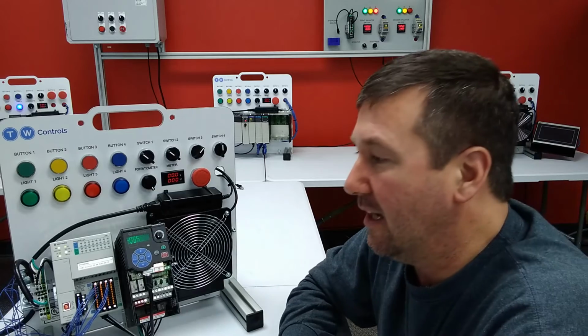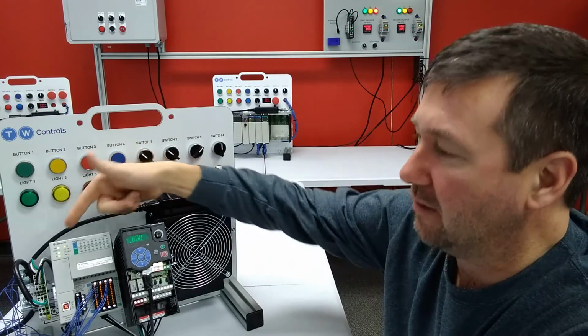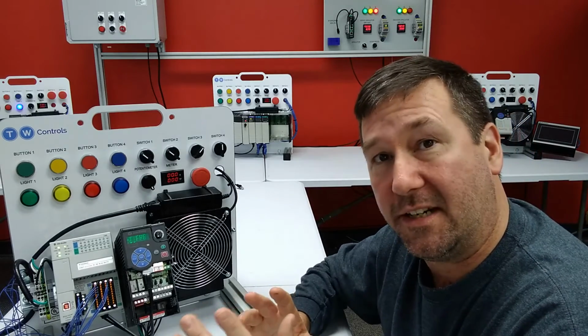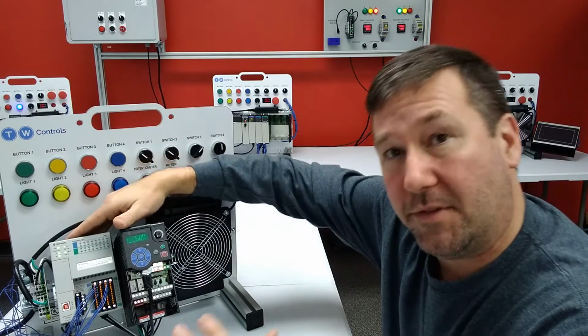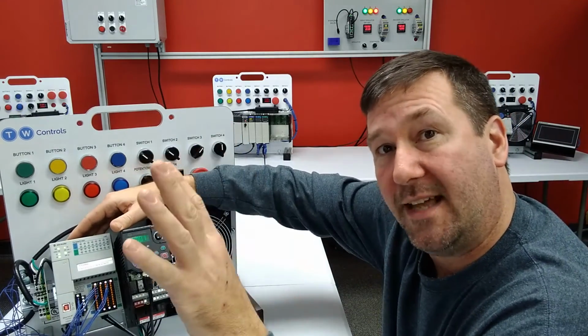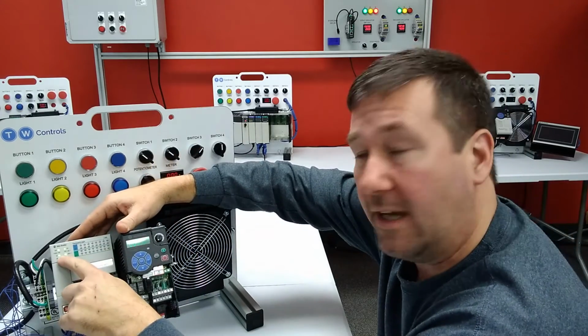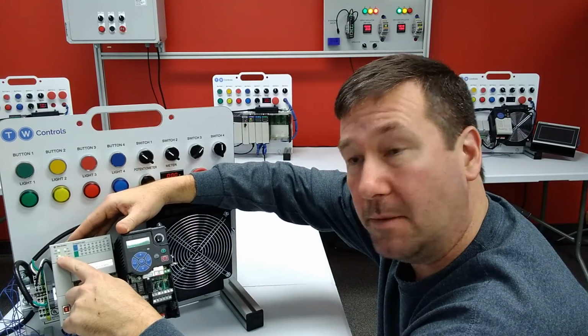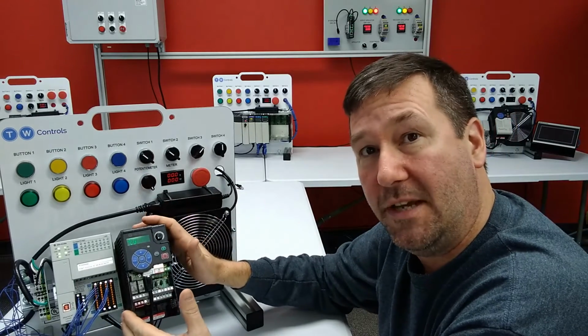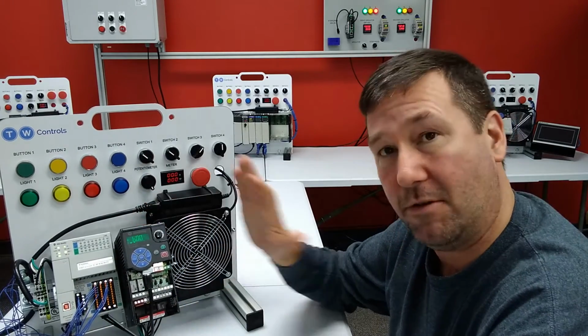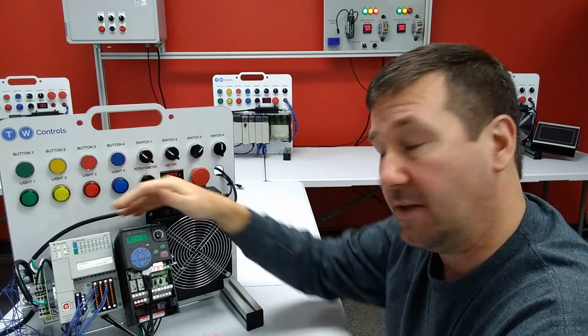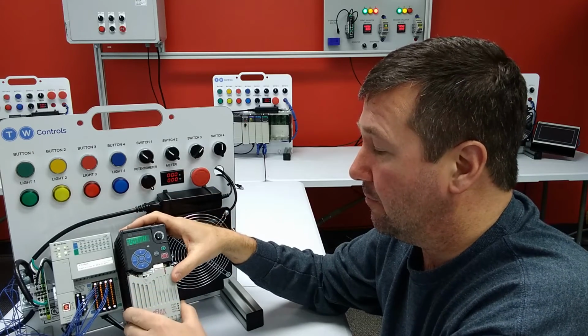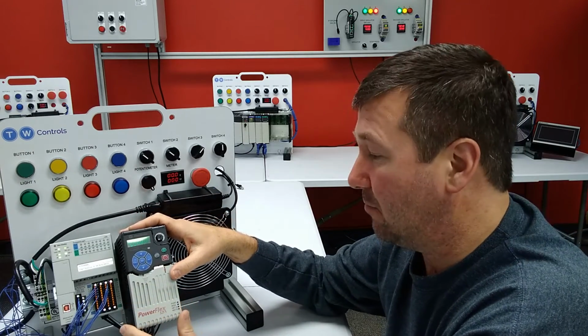but if you have gotten to this point and your IO light is still flashing, actually let's pause for a second. Okay, now my IO light's solid. So it does take it a couple of seconds, but if you have downloaded your program with just that in it and your IO light is flashing, then you have a problem. And chances are it is in your IP configuration on your PowerFlex drive, what you entered for it to communicate with. So go figure out exactly what that is.